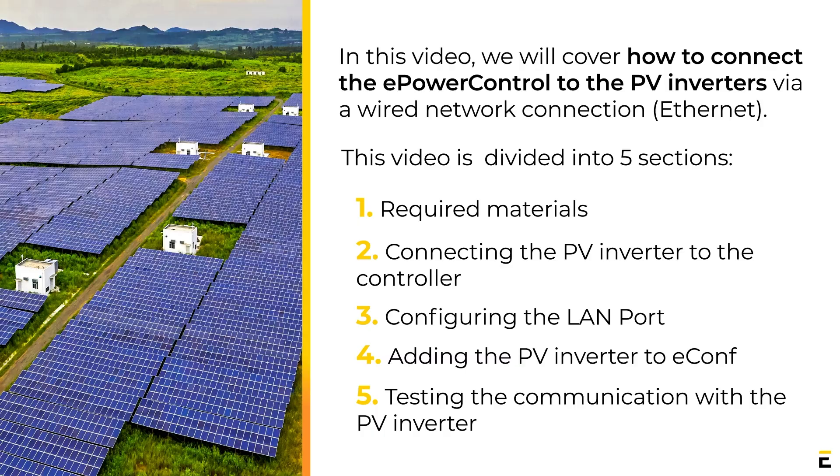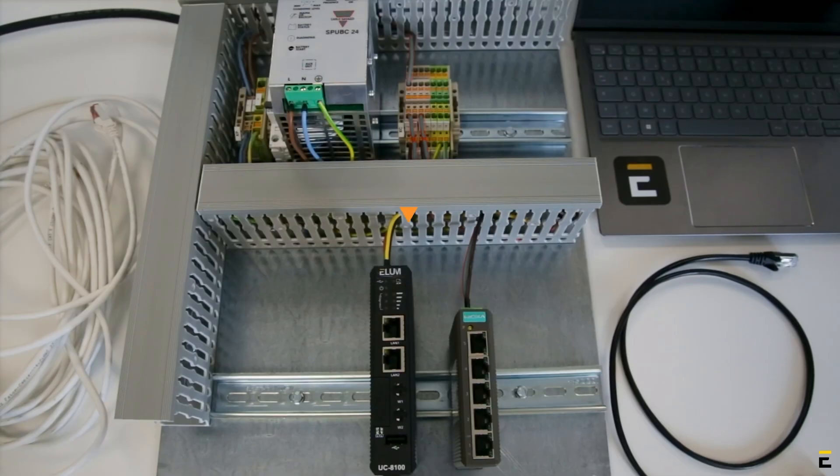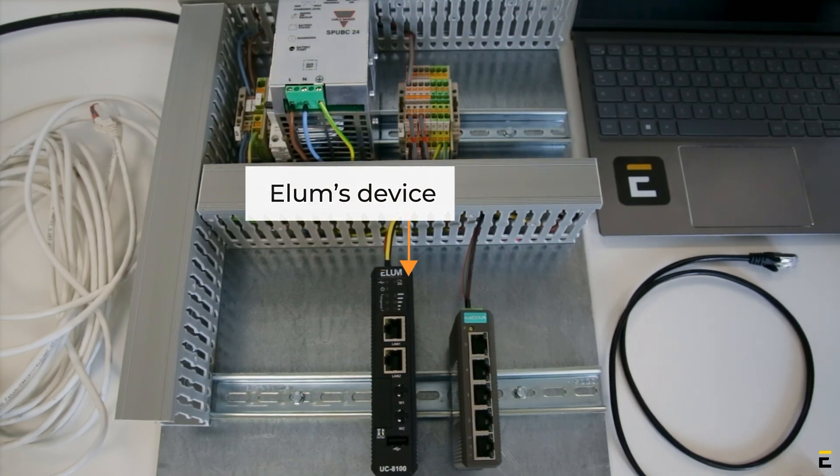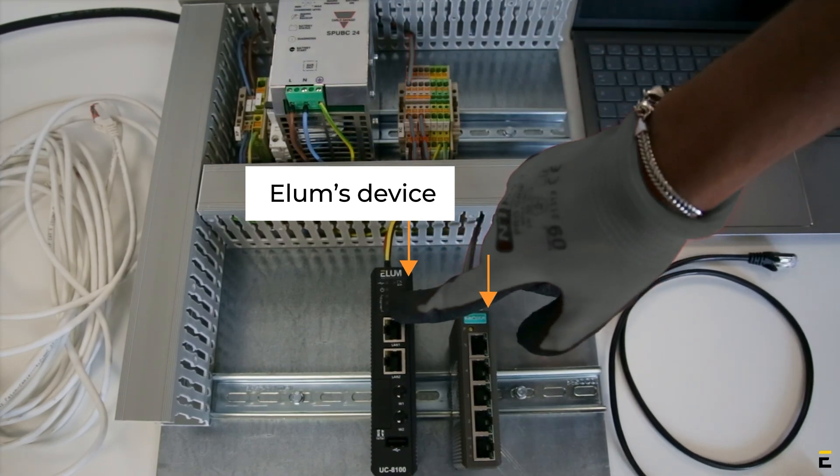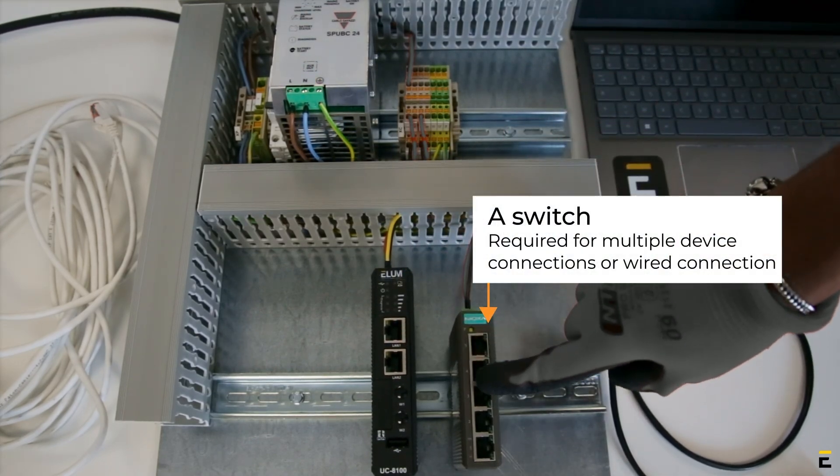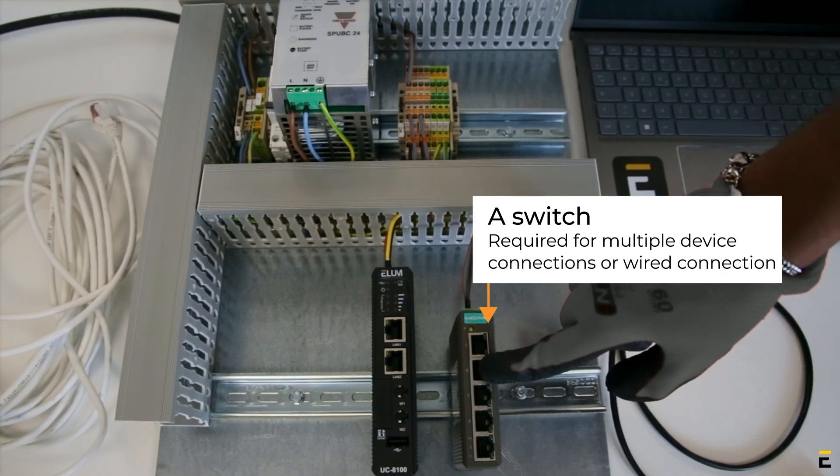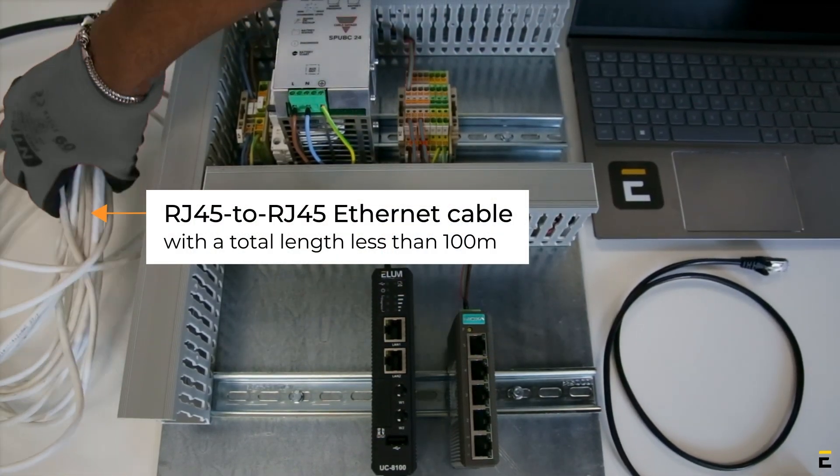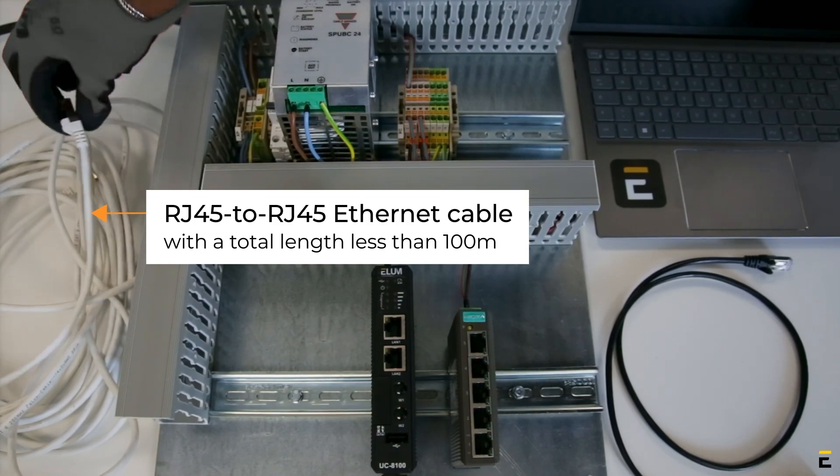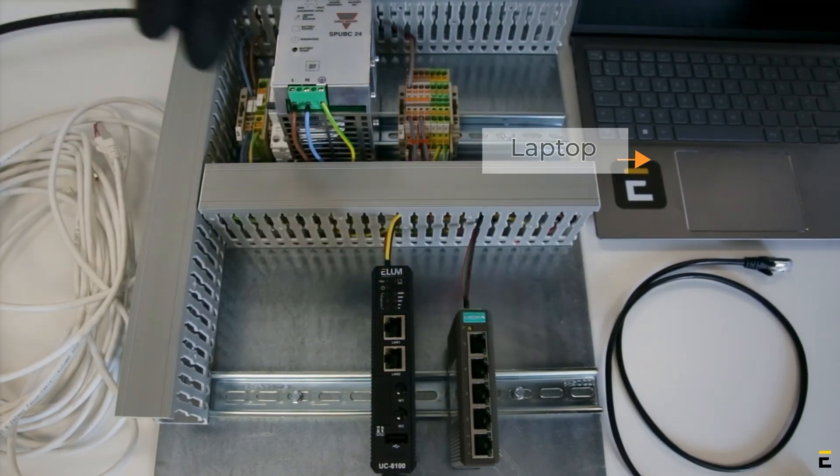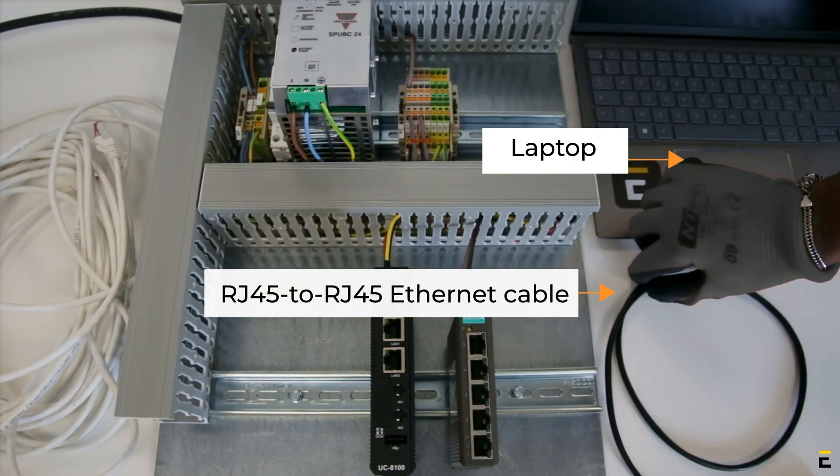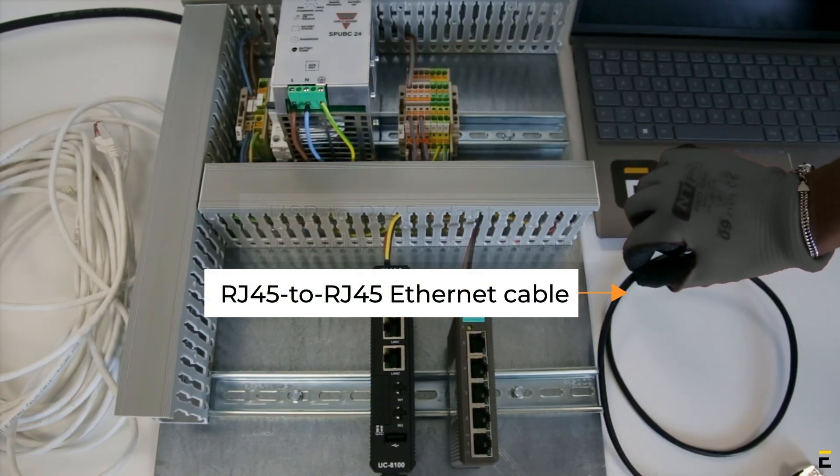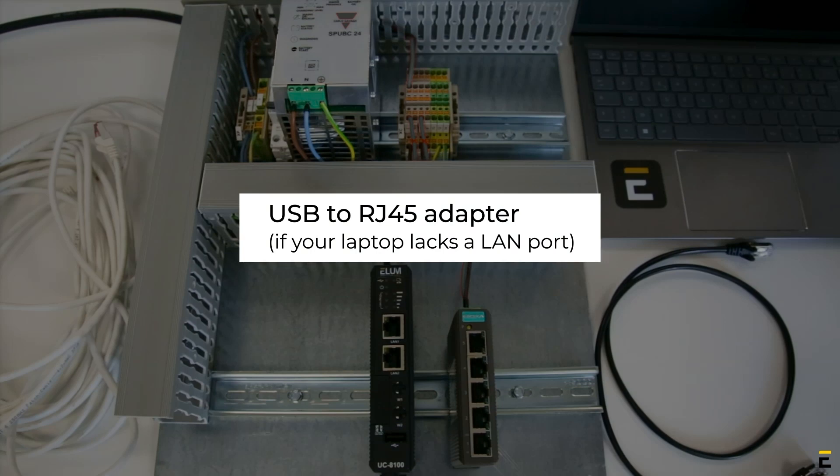Part 1: Required Materials. Elum's device and the PV Inverters are communicating in ModBus TCP. For this, we will need Elum's device, a switch required for multiple device connections or wired internet connection, RJ45 to RJ45 Ethernet Cable with total length less than 100 meters, a laptop, RJ45 to RJ45 Ethernet Cable for configuration purposes, and a USB to RJ45 Adapter if your laptop does not have a LAN port.